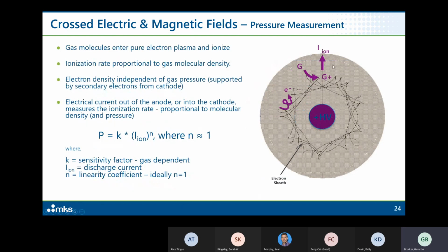The gas molecules enter the pure electron plasma and get ionized. The ionization rate is proportional to the gas density. And the magic of the magnetron discharge is that if you do things right, this electron density is independent of pressure. And if it's independent of pressure, then the ion current is linearly related to the pressure, which is great. And so literally, when you look at how you calculate pressure with an ion gauge, the pressure is proportional to the ion current, and there is usually a coefficient N there.